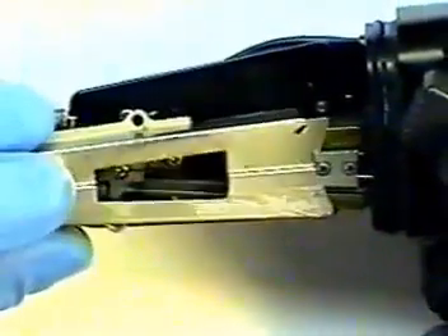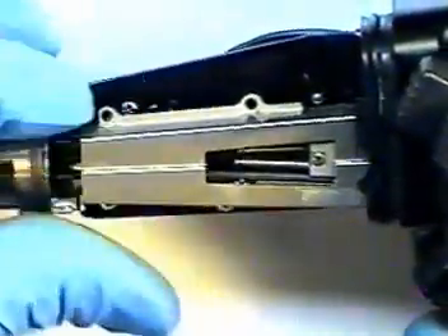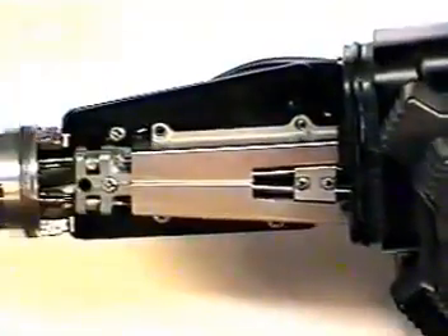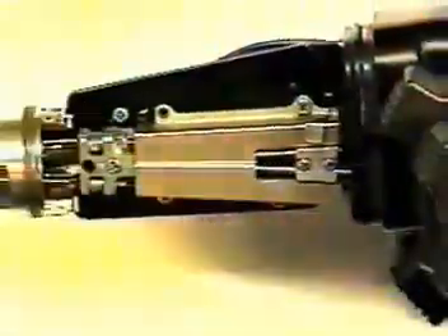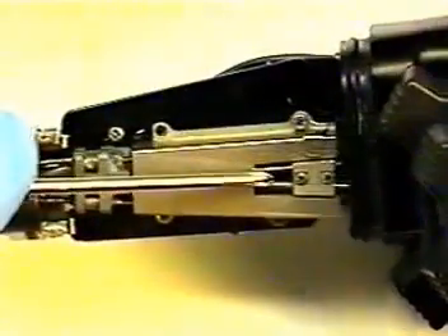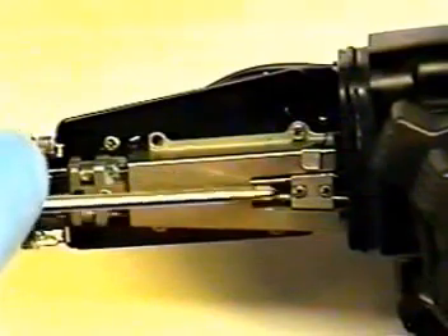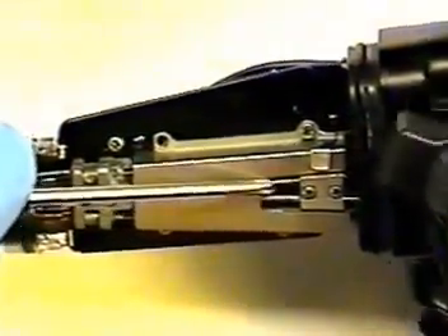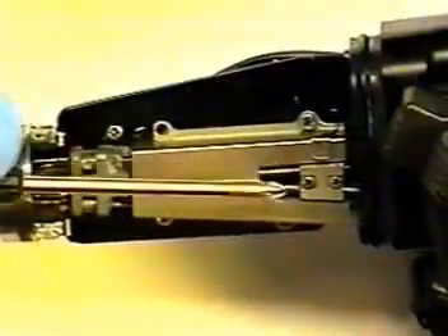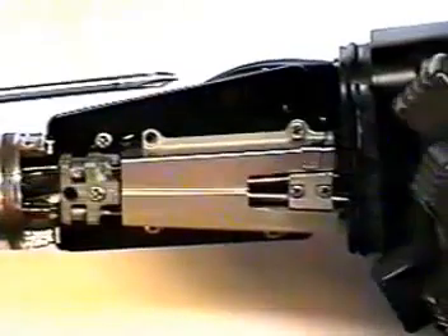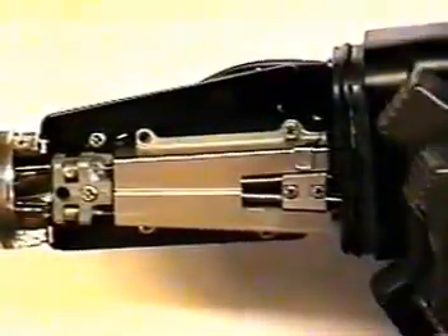Retrieve your angulation control plate and carefully slide it in, over, and down onto body section. Retrieve 4 stainless steel screws and clip, and tighten down. If previously the angulation was off, you can adjust the angulation by turning the 4 cams internally in the angulation control section. You need a flathead screwdriver and turn clockwise or counterclockwise to adjust for the proper angulation of the Fujinon scope.